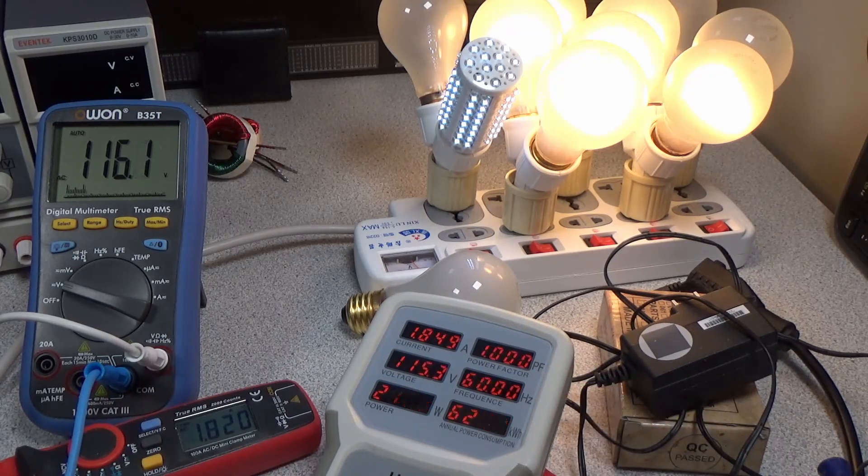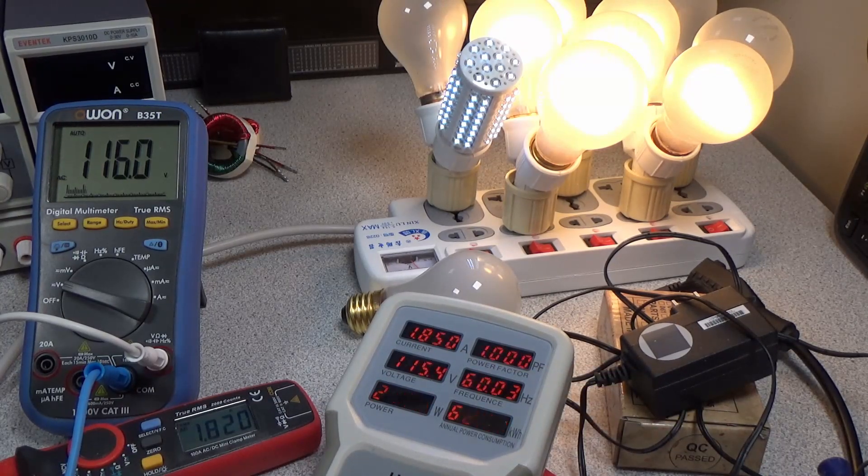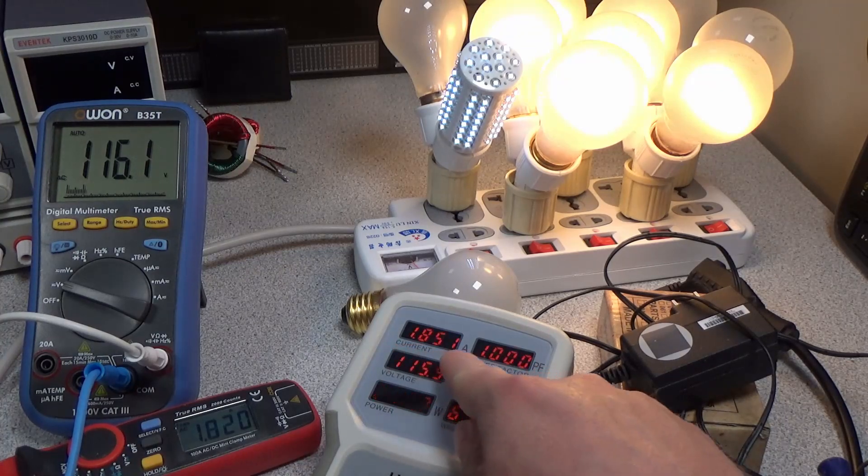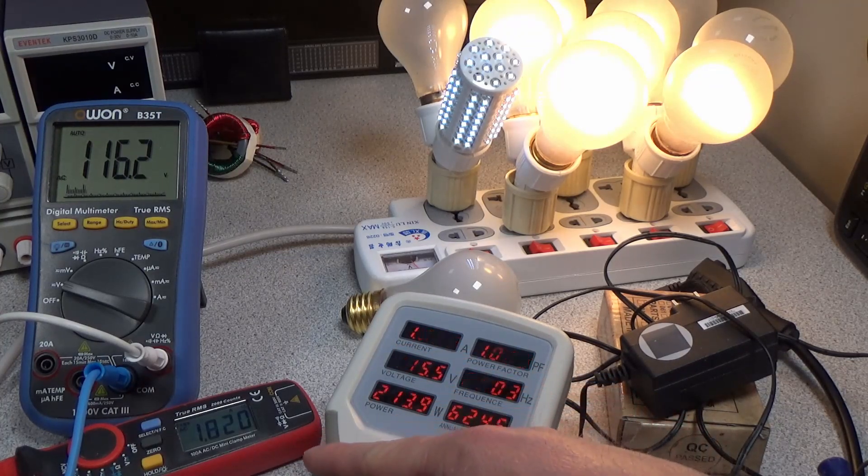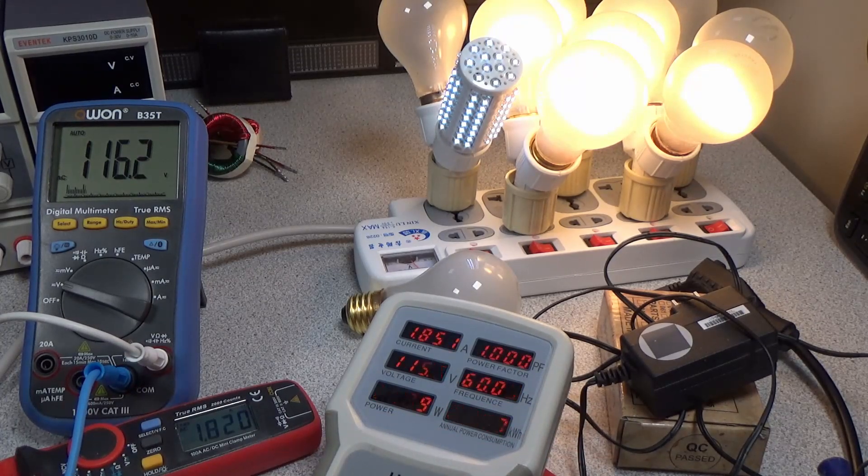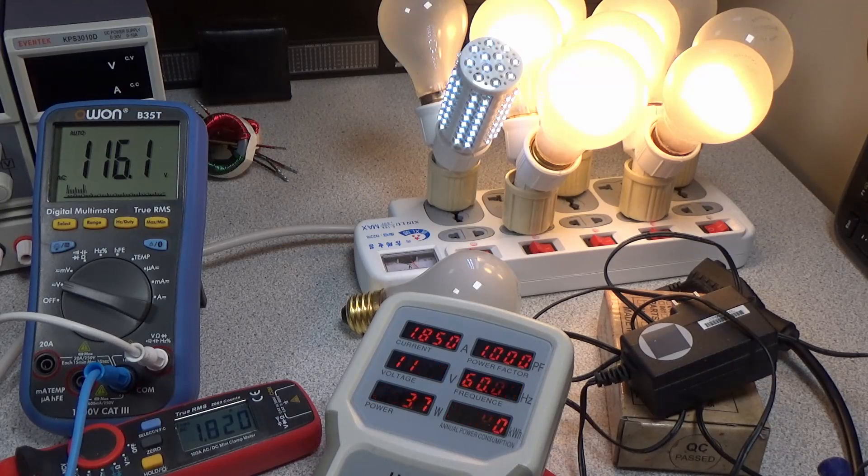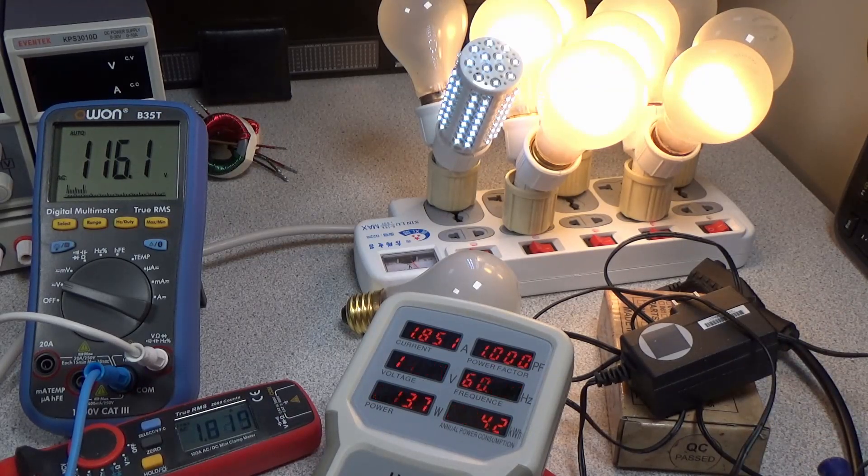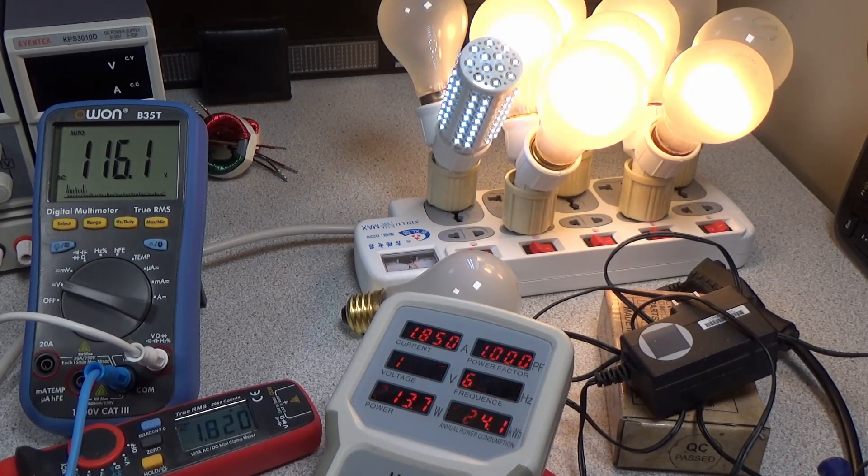We have a little bit of cable lead here, but it's all pretty heavy duty, so I don't think we have much loss there. So here we have 1.85 amps, here we're measuring 1.82 amps, they're pretty close to each other. And that power factor one, it's just the multiple of the two numbers, so these are tracking very close with each other, that's good enough.